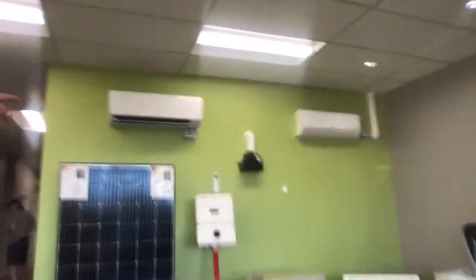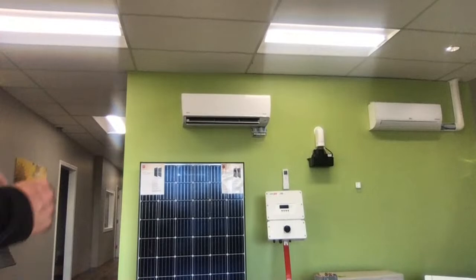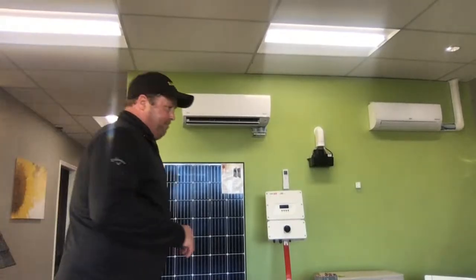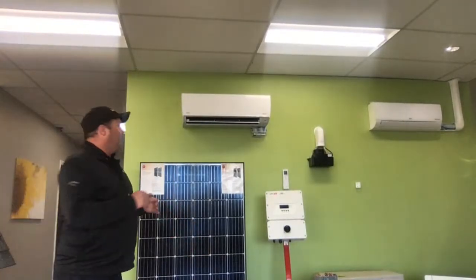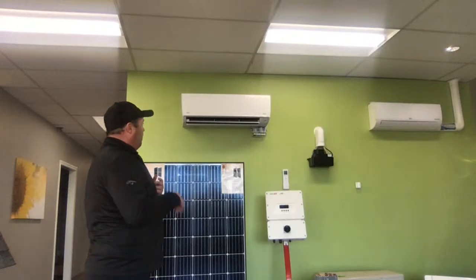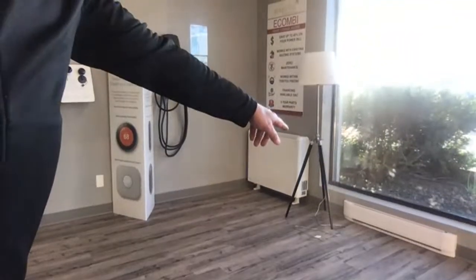But they are 2-pole, so a 12,000 BTU and 9,000 BTU unit in pretty much any brand is going to need a 2-pole 15 amp breaker. That's basically equivalent to running a little 1,000 watt baseboard heater. So they really don't use a whole lot of power.